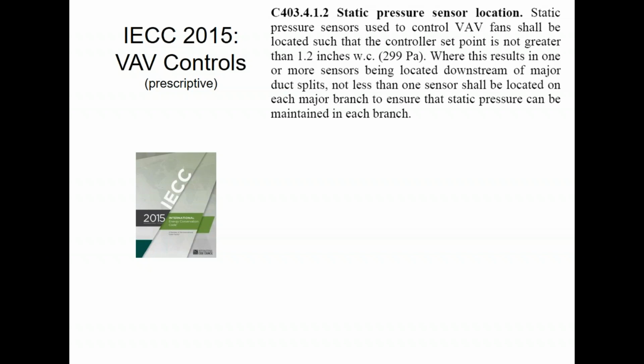That's no longer allowed. Now we need to put the static pressure sensor wherever it needs to go on the duct in order for us to have a set point of 1.2 inches of static, right? So wherever that ends up being, if it ends up being 2/3, great. If it ends up being halfway down the duct, if it ends up being 9/10 down the duct, wherever it is, that results in a 1.2 inch static set point. I don't know who chose the 1.2. I don't know why we had to pick that number. 1.5 sounds nice and round to me, but whatever. That's the number that they had picked. In some cases, this may mean you do multiple sensors if that's so far down the branch that the ductwork's already split.